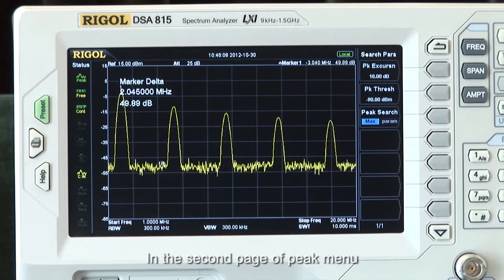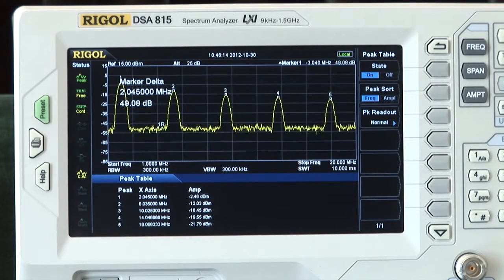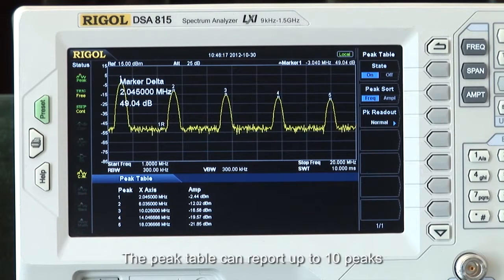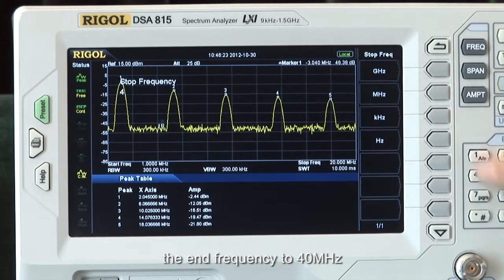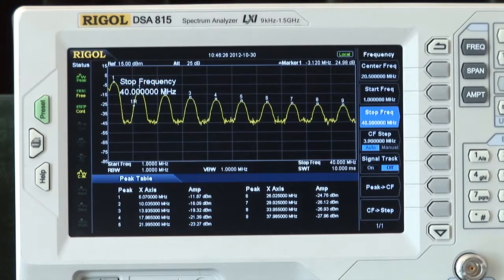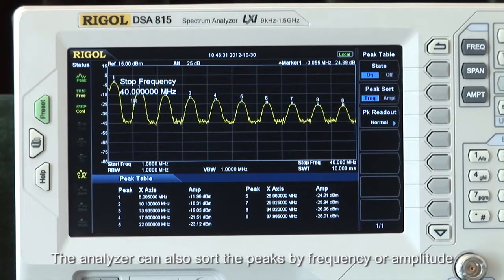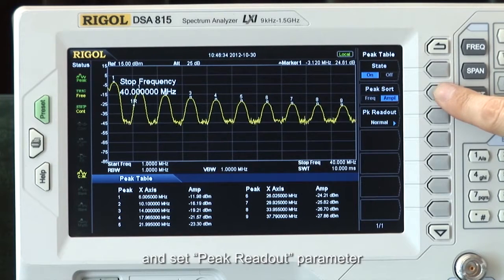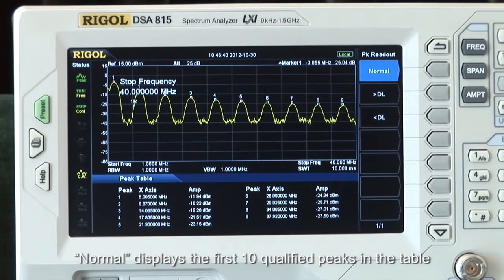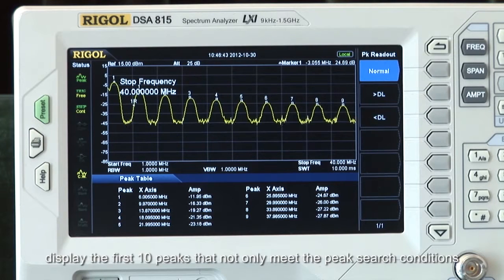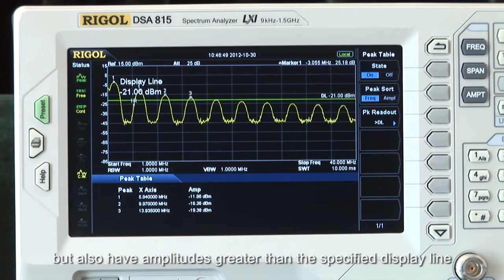In the second page of the peak menu, peak table displays the peak values which meet the search parameters. The peak table can report up to 10 peaks. We can use the peak table here by setting the end frequency to 40 MHz, so now we can see more harmonics of the input square wave. The analyzer can also sort the peaks by frequency or amplitude and set peak readout parameters. Normal displays the first 10 qualified peaks in the table. Greater than the display line displays the first 10 peaks that not only meet the peak search conditions, but also have amplitudes greater than the specified display line.